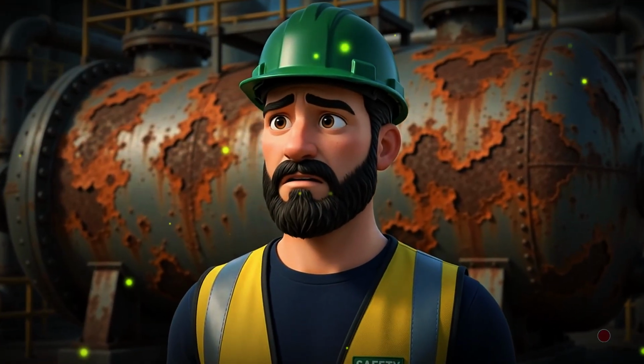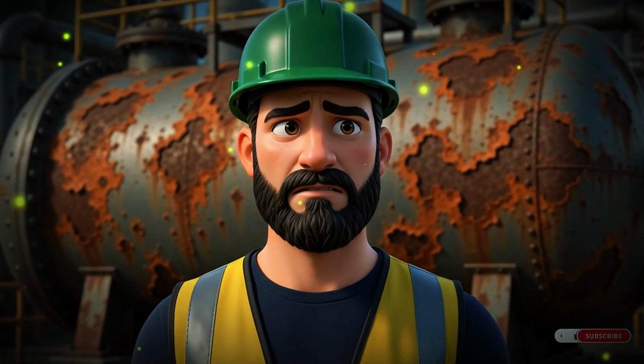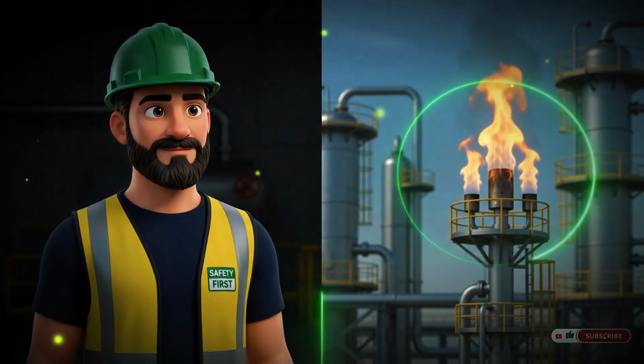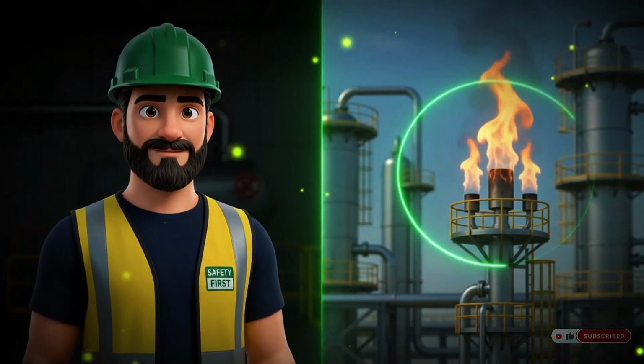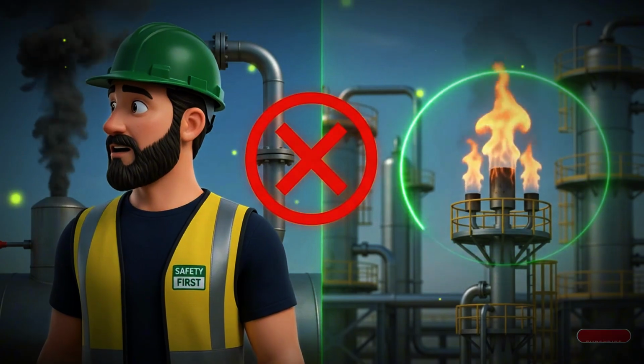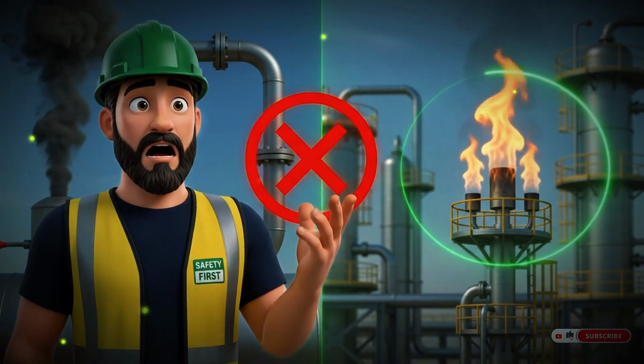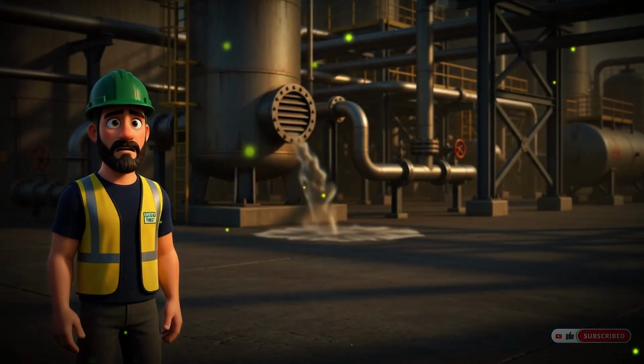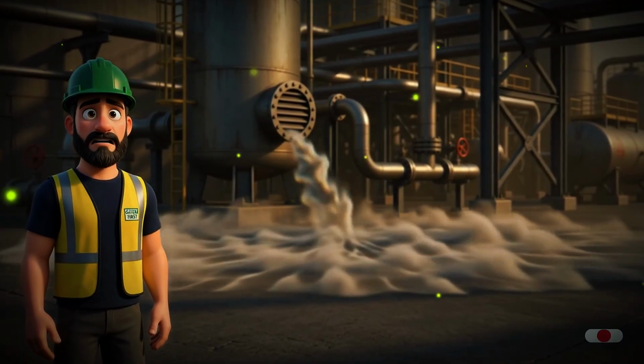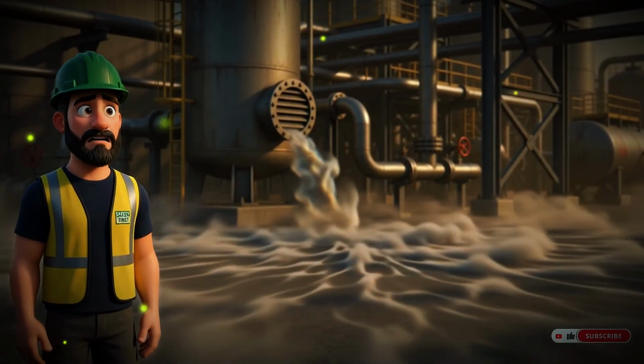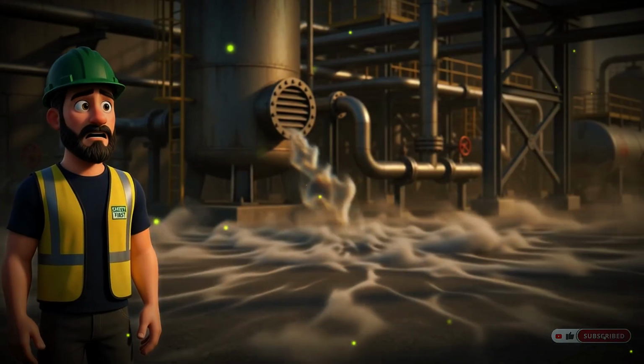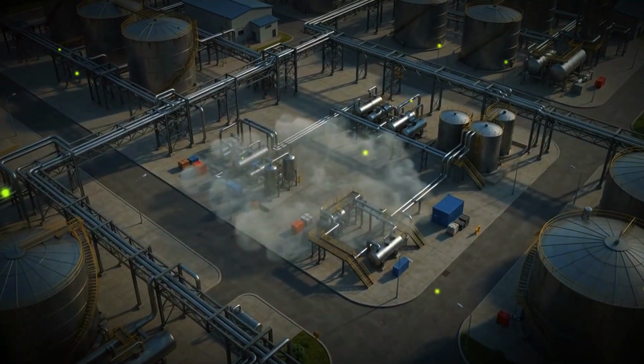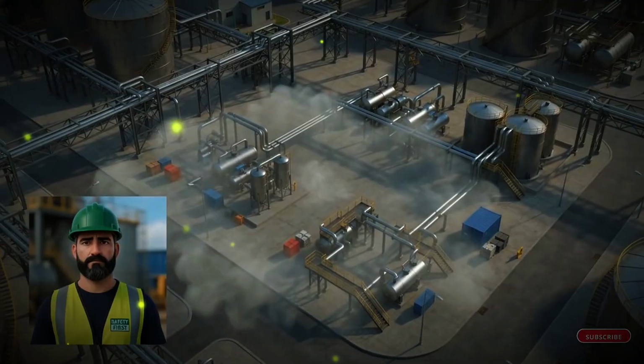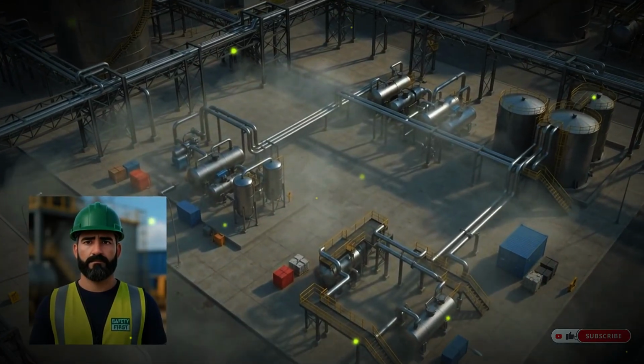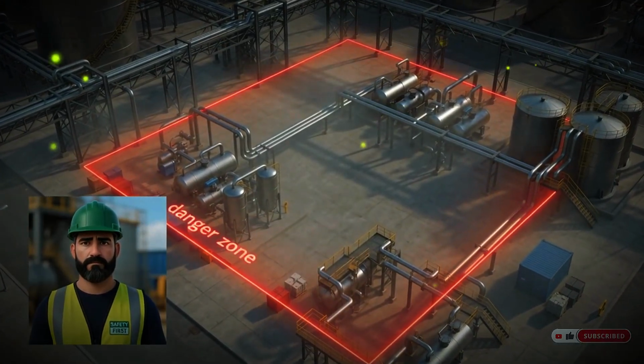But there was an additional problem equally serious. The blowdown drum was corroded, had not been adequately inspected in years, and most critically, it was not connected to a flare system, those industrial torches that refineries use to safely burn off relief gases. Instead, the drum vented directly to the open atmosphere. The result was the creation of a massive cloud of highly flammable hydrocarbon vapor at ground level, spreading around the unit. An invisible cloud, heavier than air, silently drifting for dozens of meters in every direction.